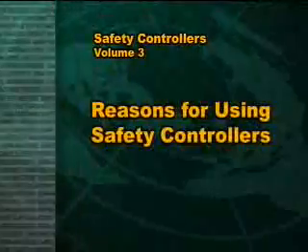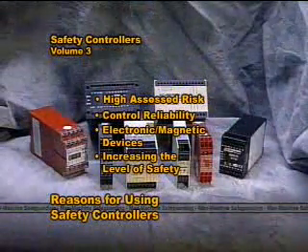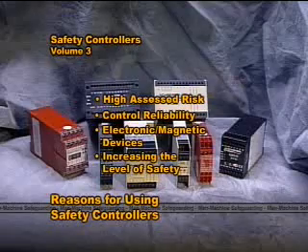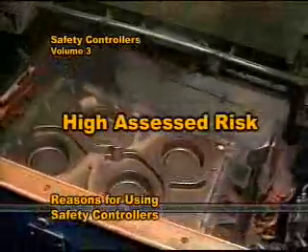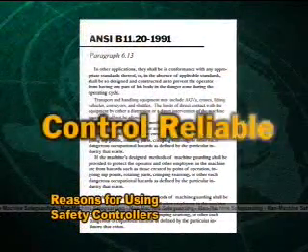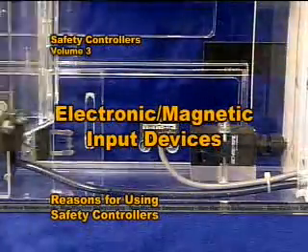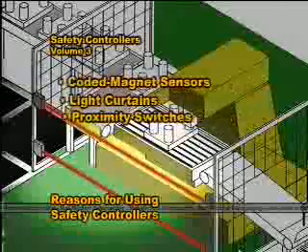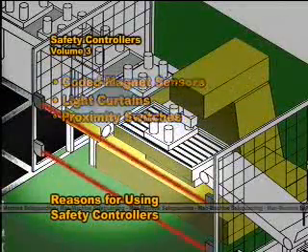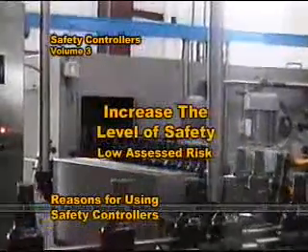Now let's move on to understanding the reasons and applications where using a safety controller is recommended. There are a variety of circumstances in which use of a safety controller is recommended or required. These include, but are not limited to: applications in which the assessed risk of severe injury and frequency of exposure to recognized hazards is relatively high; applications for which the designer wishes to satisfy ANSI control reliability requirements; safety applications using electronic or magnetic input devices, such as coded magnet sensors, light curtains, or proximity switches, which by their design may not fail to a safe condition; and applications having a relatively low level of assessed risk, but for which the designer wishes to heighten the performance or reliability of the safety system.